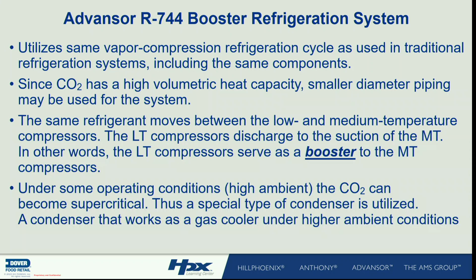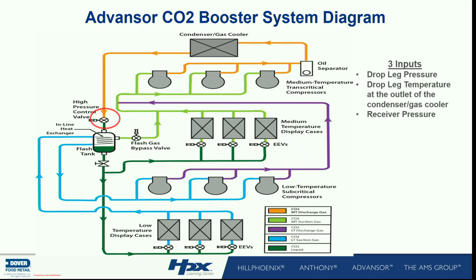So when we start looking at these systems, this is a basic drawing, yes? And if you walk into any of these racks and look at the Emerson rack, they Europify it. I'm going to make it look American, that's how I roll. So this is quite simple. Is this a simple rack? Look at it, it's a very simple rack. But what makes this rack different? Everything else here is the same, but what makes this a wee bit different is the high pressure control valve and the flash gas bypass valve.